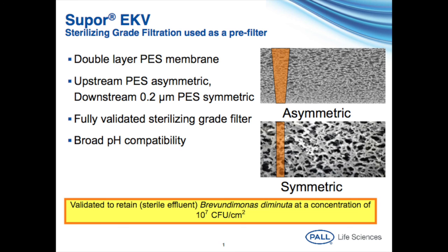SUPOR-EKV is a fully validated sterilizing-grade filter with broad pH compatibility. However, with these high-risk fluids, SUPOR-EKV should be employed as a pre-filter to another filter that we found to have high throughput and recovery with full retention of bacterium. That filter is Fluorodyne EX-EDF. I will be discussing Fluorodyne EX-EDF at the end of my presentation.